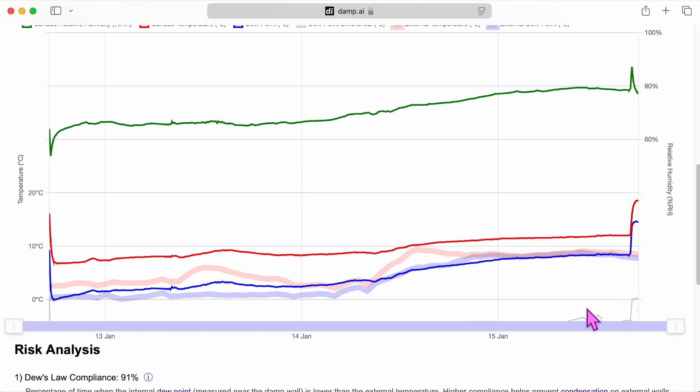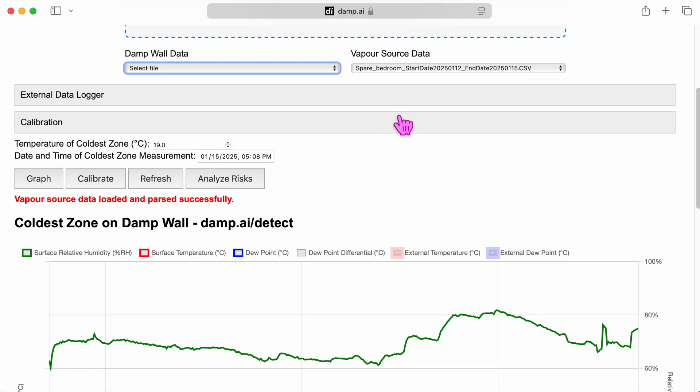It shows that a lot of vapour is being generated in the spare room. To sum up, the key findings are that mould was growing behind the cupboard — it's generic, growing in many more places, within the cupboard, and on the other side. So it's a vapour issue. The reason it's growing there is because of heat loss in the corner. Past damp proofing treatment reduces absorption of vapour, making it worse. The best thing to do is insulate in around there, as well as reduce the vapour from the bathroom, drying clothes, and the kitchen. Use the data loggers going forward to see what's happening.